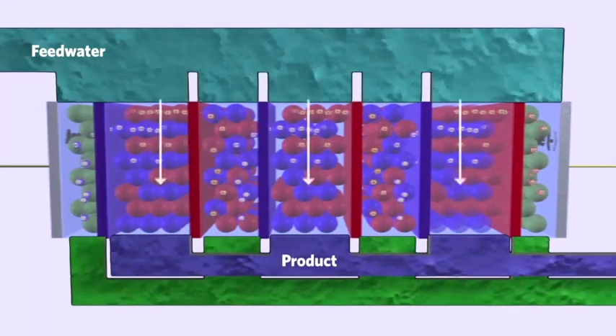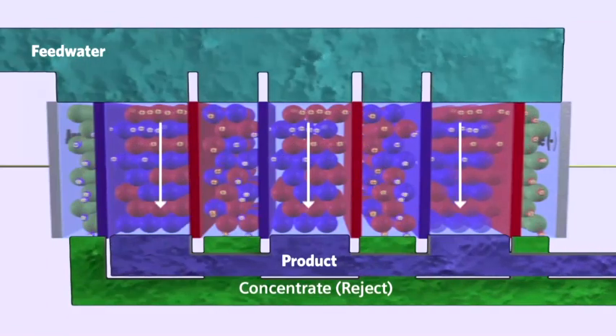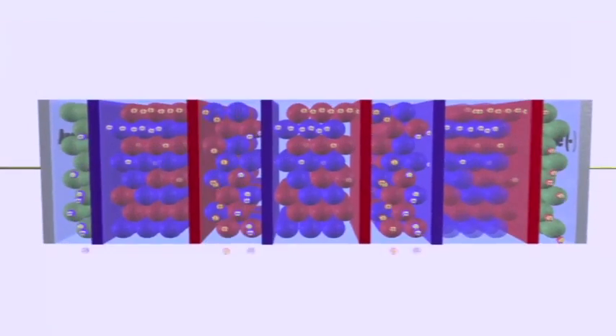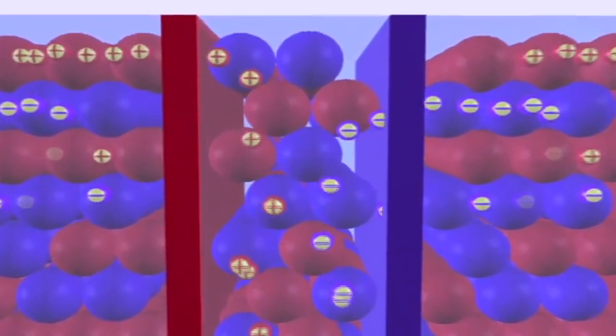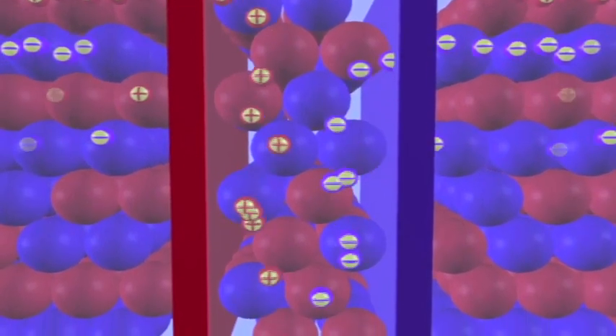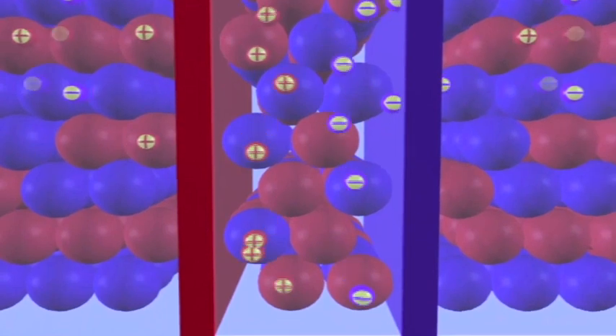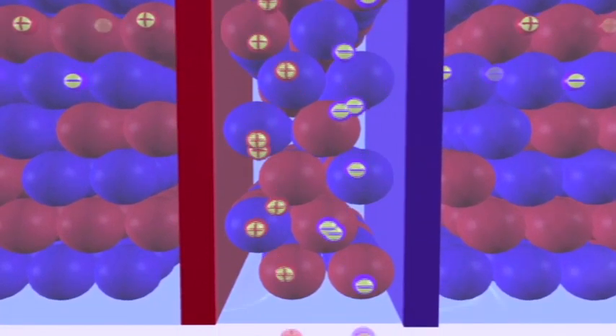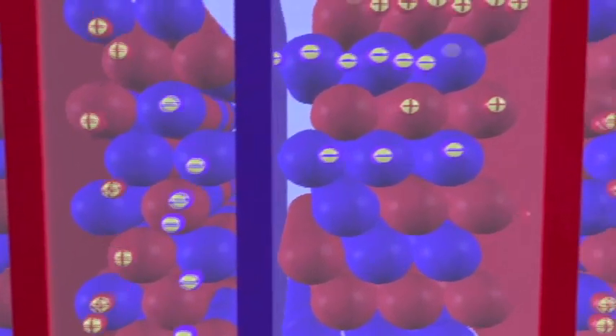These water streams remain separated throughout the process because only ions can pass through the membranes. Ions migrate and accumulate in the concentrating compartments, where they are washed away into the reject stream. The water leaving this compartment contains a concentration of ions approximately 10 to 20 times higher than the original feed water. This water may be drained, recycled, or reclaimed for further treatment.